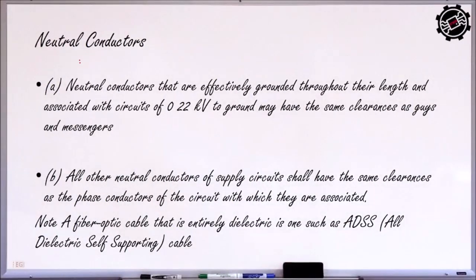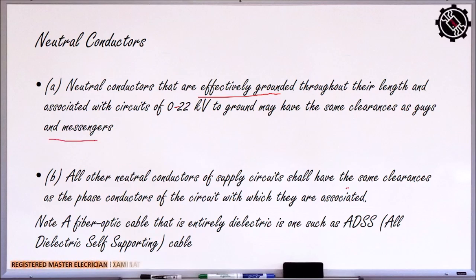Okay. The neutral conductors. Neutral conductors that are effectively grounded throughout their length and associated with circuits 0 to 22 kilovolts to ground may have the same clearance as guys and messengers. All other neutral conductors of supply circuit shall have the same clearances as the phase conductors of the circuits with which they are associated. No?